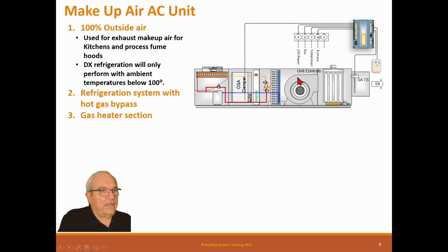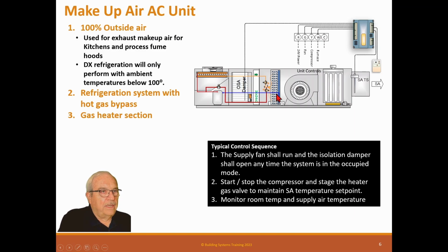Refrigeration system with hot gas bypass. It has hot gas bypass, so it can do its job when it's colder temperature. A gas heater section. The supply fan should run, and the isolation damper should be open anytime the system is in the occupied mode. Start, stop the compressor. Stage the heater gas valve to maintain supply air temperature set point. Monitor room temperature and supply air temperature.